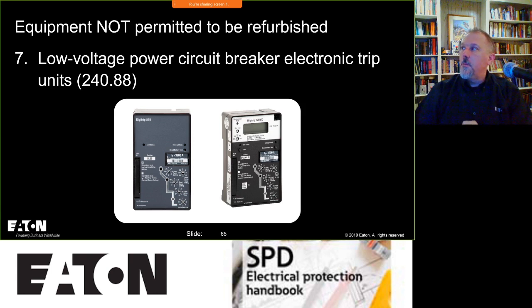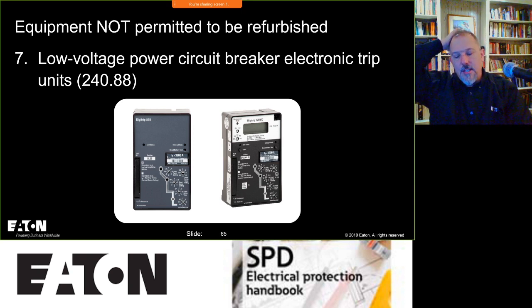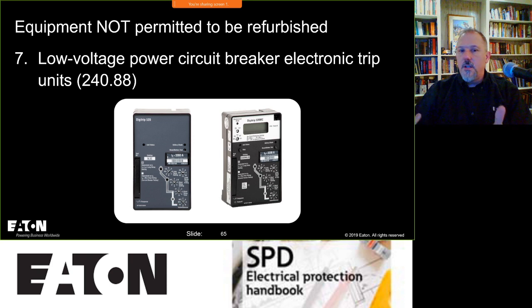Low voltage power circuit breakers have electronic trip units. Now, when you start seeing electronics, you're not going to be taking electronic parts, soldering on the board, and putting those things back into service. These are very critical for arc flash reduction and things of that nature. You may be permitted to recondition a power circuit breaker, but you're not permitted to recondition these trip units.